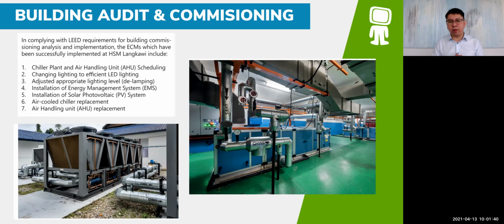Next is the solar photovoltaic system, that's number 5. Number 6 is the air-cooled chiller replacement. The project used an air-cooled chiller rather than a water-cooled chiller for a few reasons: the municipal water supply was not enough, and the hospital is located at the seaside, on an island, so the humidity and environment weren't suitable for installing a cooling tower there. An air-cooled chiller was a better option for the air conditioning system.